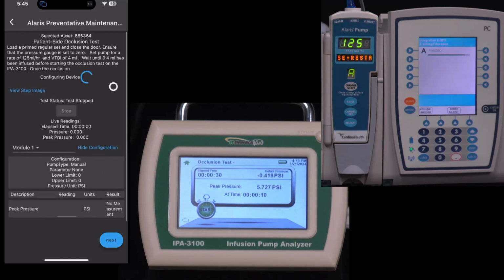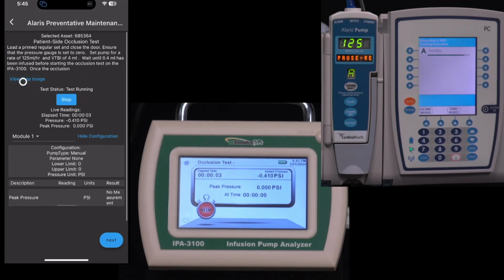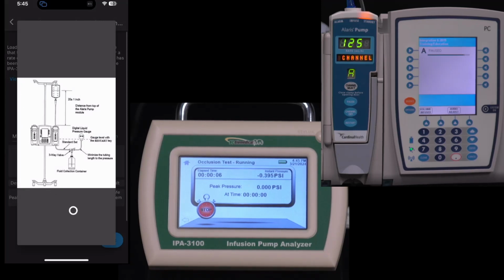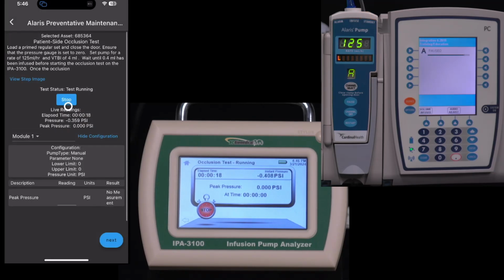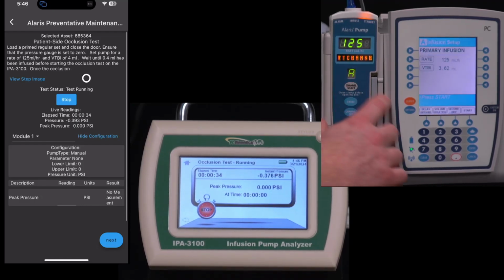Now we're getting to that automated testing. So this is a neat thing that we have in MyBC Mobile in our test sequences. You can load a picture of what my configuration should look like. What should this test be? So this shows me all the connections. This is a picture straight from the service manual, but it's already configured the IPA. It started the test for the occlusion test, and I can follow my instructions that are up here. Again, we entered these straight from the service manual, so we'll go ahead and configure the pump.